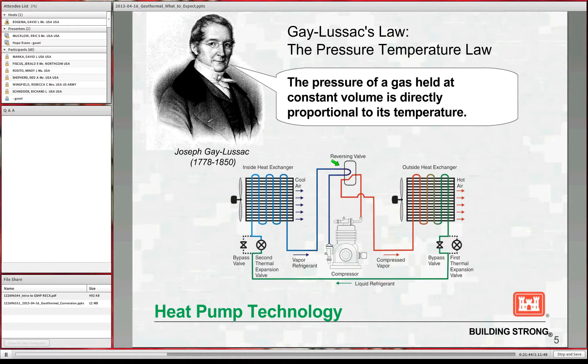So each heat pump fundamentally has these components, as you see below. They essentially have the same thing on two different sides, one being a coil with a fan blowing across it, a couple of valves, same on each side, and then a compressor and a reversing valve. The reversing valve simply allows it to switch between cooling mode and heating mode, so we don't need to go too much into that. We'll just talk about the cycle of what's happening and how this thing heats and cools your house.